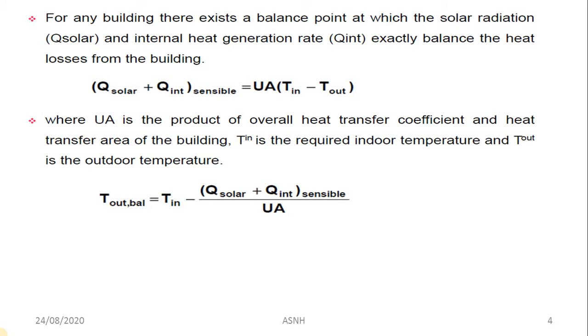So here this is the equation: Q solar plus Q internal heat gain for sensible condition is equal to UA times the difference between inside and outside temperature. UA is nothing but the overall heat transfer coefficient. So this is the most important equation. Further, UA is the overall heat transfer coefficient times the heat transfer area of the building, and T in is the required indoor temperature and T out is the outdoor temperature. So this is the equation through which we can calculate the UA values manually.